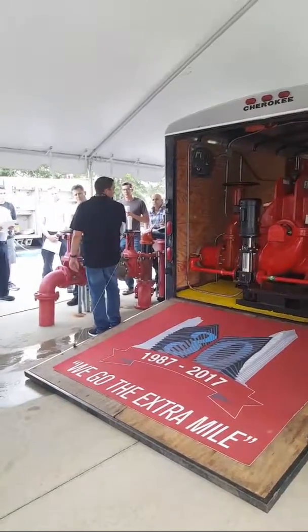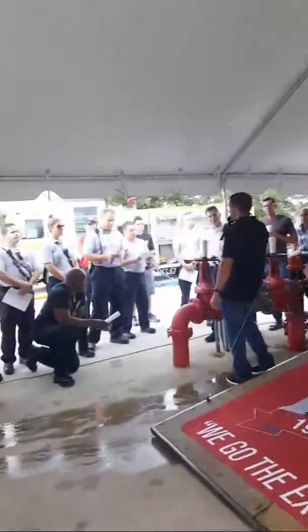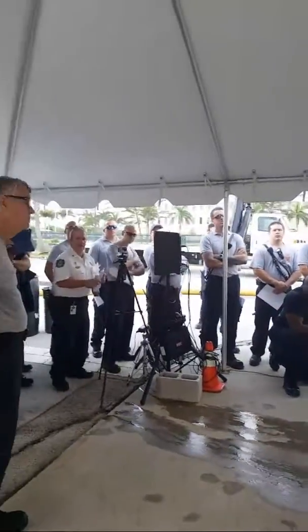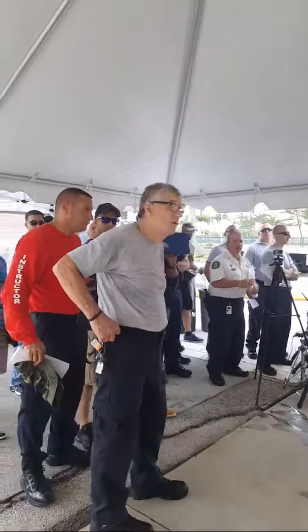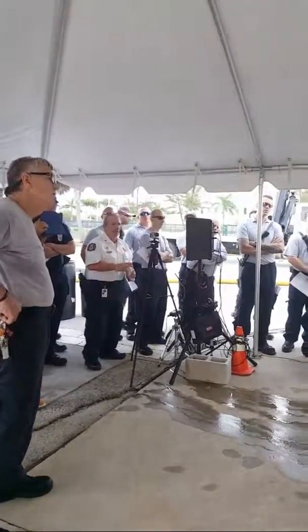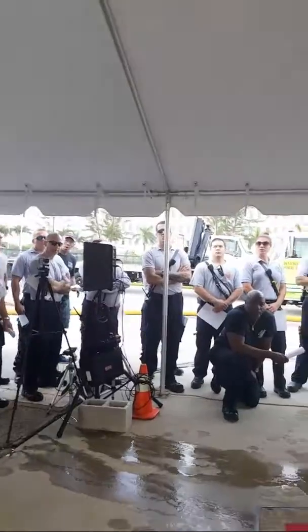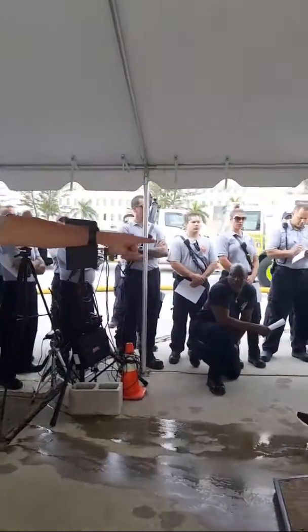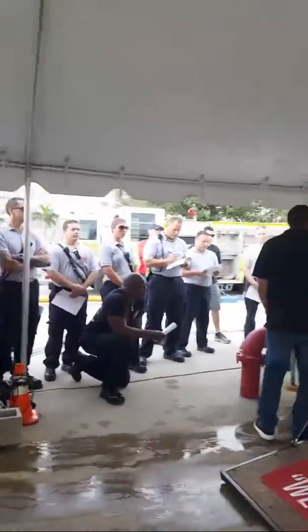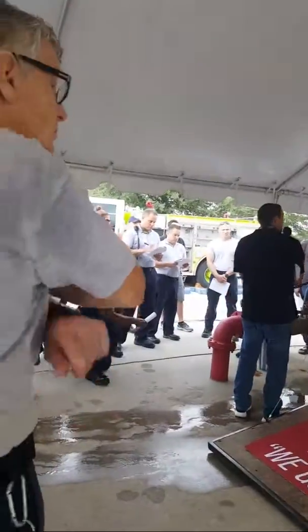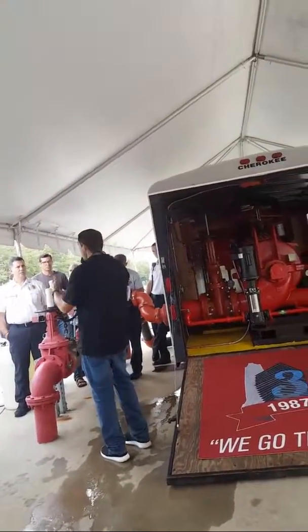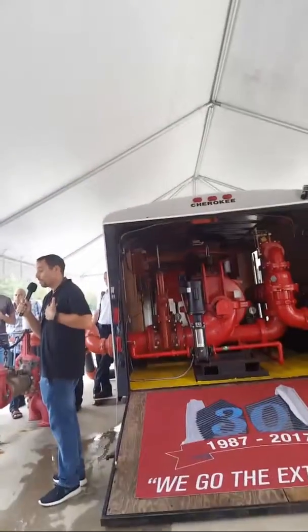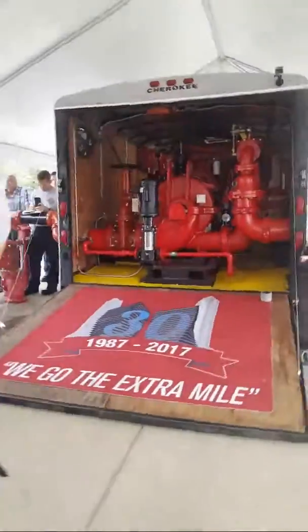At about 80 PSI, Greg? I think we're discharging 140, so 140 less your suction. And what would it be capable of doing if it wasn't for that restriction? We have a 6-inch supply on this fire pump, but it can take a 10-inch supply. It's really rated for 2,500 GPM, but for all intents and purposes, and what we tested it at here, we can flow about 1,180 gallons out of here.